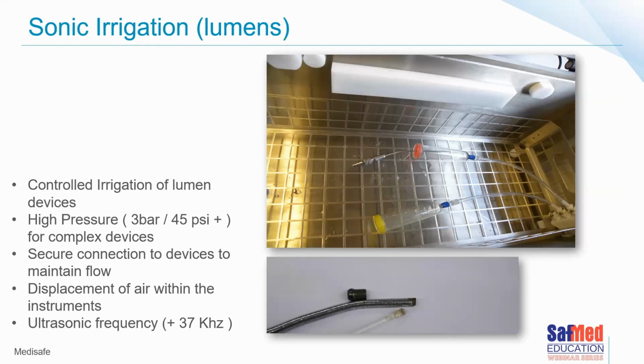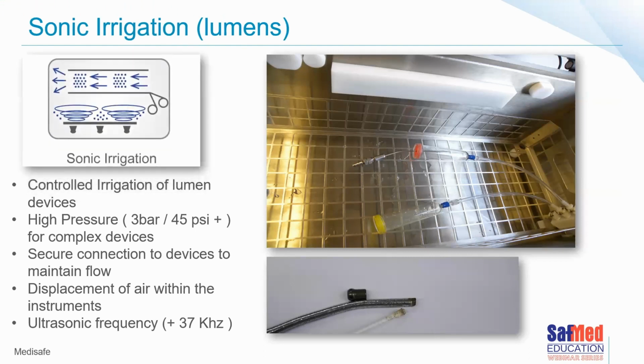Here's an image of a fine sucker, or plastic sucker, a number of different names for this very fine suction that you can see connected to the device. It's using a specific connector. This type of ultrasonic cleaner will clean the inside of the device as well as, we said, ensuring a lumen sonic irrigation or flush. Each make and model will specify the ultrasonic frequency as well as the pressure for flushing, and that could be around about 3 bar, for example.